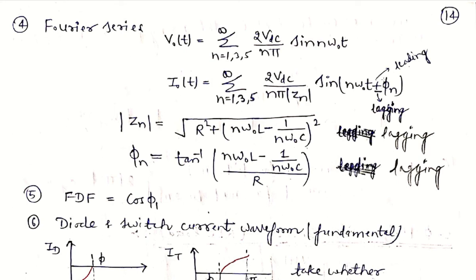The impedance for the lagging load case is: Zn = √(R² + (XL − Xc)²), where XL = nω₀L. The harmonic number is n, and the power factor angle is: φn = tan⁻¹((nω₀L − 1/(nω₀C)) / R), which is XL minus Xc divided by R for the lagging case. For the leading load case, simply substitute Xc greater than XL in these expressions.